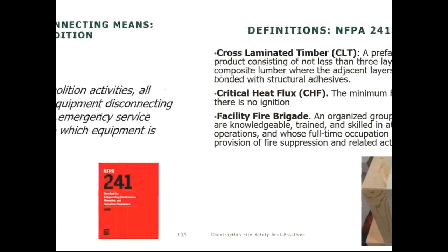So just like in anyone's house, when there's a fire, some fire companies are assigned to shut off the utilities. You don't want to be throwing water around live electrical services. So during construction, you have to have a single switch that shuts off all of the electric to the whole project. Yeah, that's why every branch circuit has to originate in a panel board or power outlet.